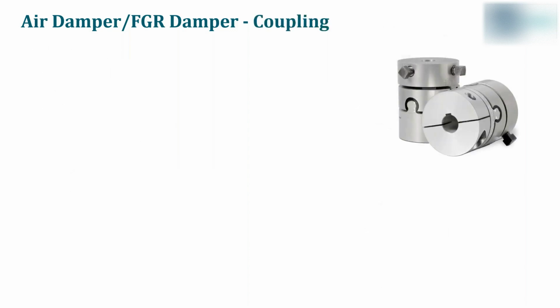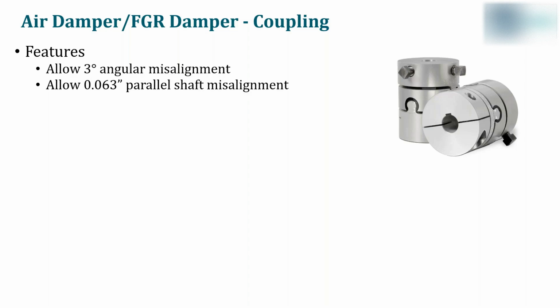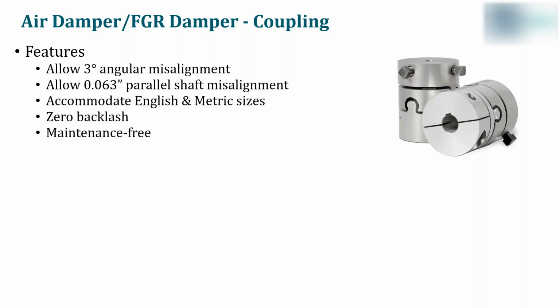Now, for an assembly, there are two components required, a coupling and a bracket. We will cover both and how to size it. First, we'll do the coupling. Features of the coupling: they allow for 3-degree angular misalignment. They allow for 63 thousandths of an inch parallel shaft misalignment. They accommodate English and metric sizes, zero backlash, and finally, they're maintenance free. The flexible coupling design, in this case, minimizes the side loads on the actuator and the valve shafts due to minor misalignment, which in turn helps prevent actuator binding and improves control performance and reliability.